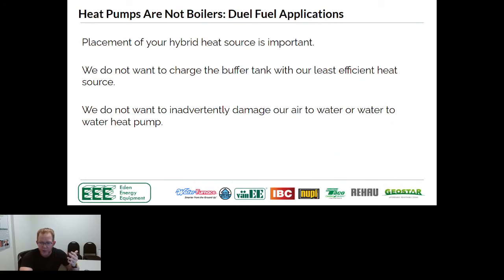A couple of things we keep in mind: if we have a buffer tank on the system, we don't necessarily want to be charging that buffer tank. My preference is to let the hydronic heat pump charge the buffer tank and then use whatever your backup heat is to actually heat the building itself. There's no reason to heat and store that energy, but there's a lot of different perspectives. There's a lot of different ways to do it. Happy to dive into that more.